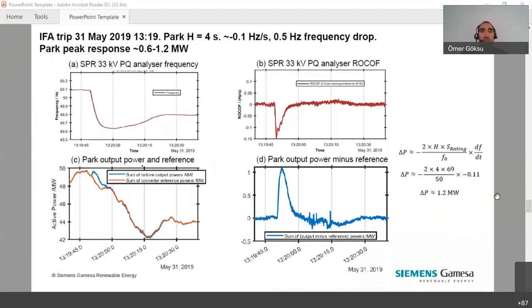And then luckily there was an event during these tests. It was an interconnection tripping, which was about 1 gigawatt of loss and a 0.5 hertz drop, as you can see on the top left, with the rate of change of frequency reaching or exceeding 0.1 hertz per second. The farm output, which you can see on the bottom left, is increasing by 1.2 megawatts, as calculated here. So the farm was responding to this real frequency event, and the difference between the reference and actual output can also be seen here on the bottom right figure.